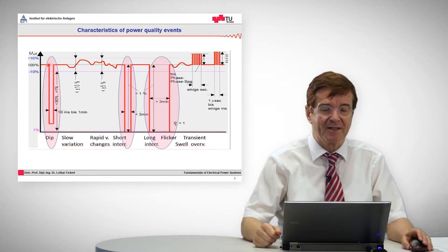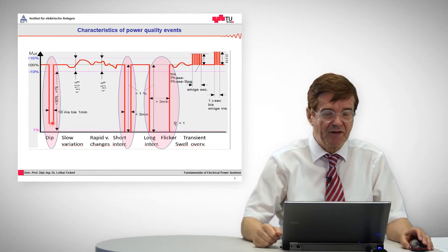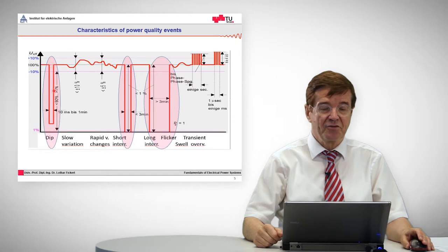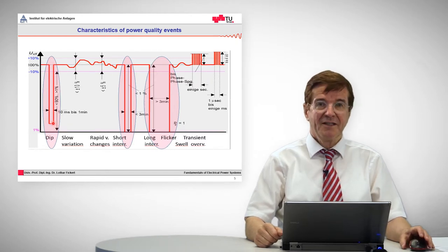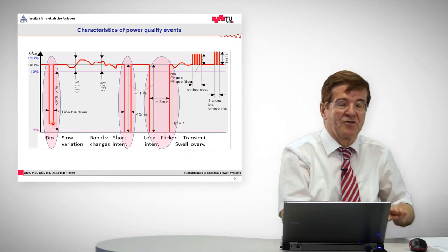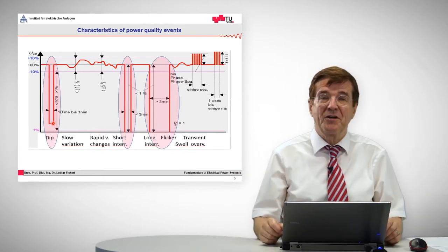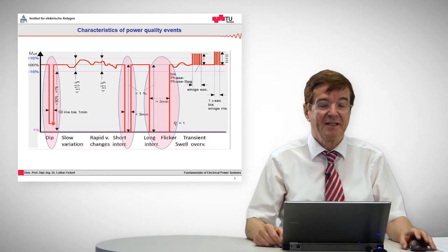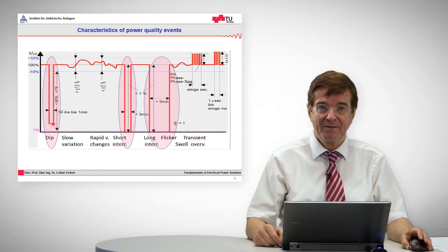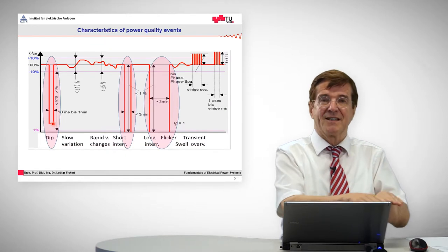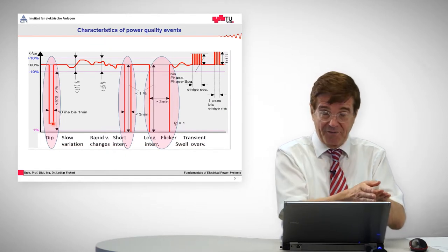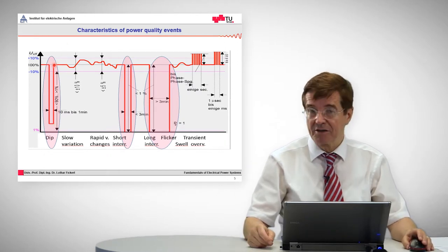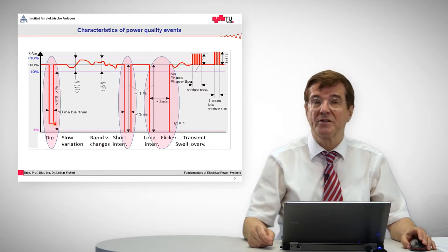Let us look at what happens when the voltage goes down to very low values — something like 10% of the nominal voltage. That is due to a short circuit somewhere in the grid. At the point of the short circuit, the voltage goes down to zero. In the surrounding area, we have some residual voltage, also in the order of 5 to 10%, and that is felt by everybody in the grid. This low voltage persists as long as the short circuit current is flowing, but when it is tripped off, the voltage recovers and we have our good and perfect voltage again. These events are called voltage dips.